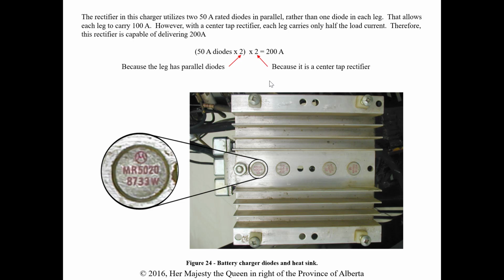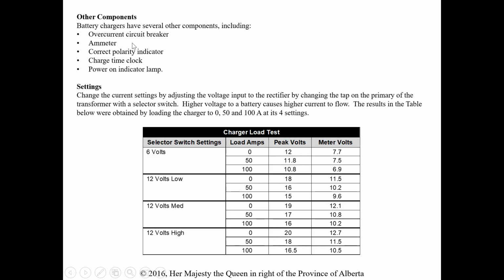So if they said, I have a 200 amp load, what size do the diodes need to be? Well, it's literally just the opposite. You would just start at the 200 and work your way back and divide by 2, and then you'd get your rating. Okay. Other components they have: overcurrent circuit breaker, an ammeter, correct polarity indicator, charge time clock. Again, this is usually a timer because you don't want to leave your batteries charging unattended for extended periods of time, because it could overcharge and then the battery explodes and smokes out, and could cause a fire too. Okay, so they're usually on a timer.